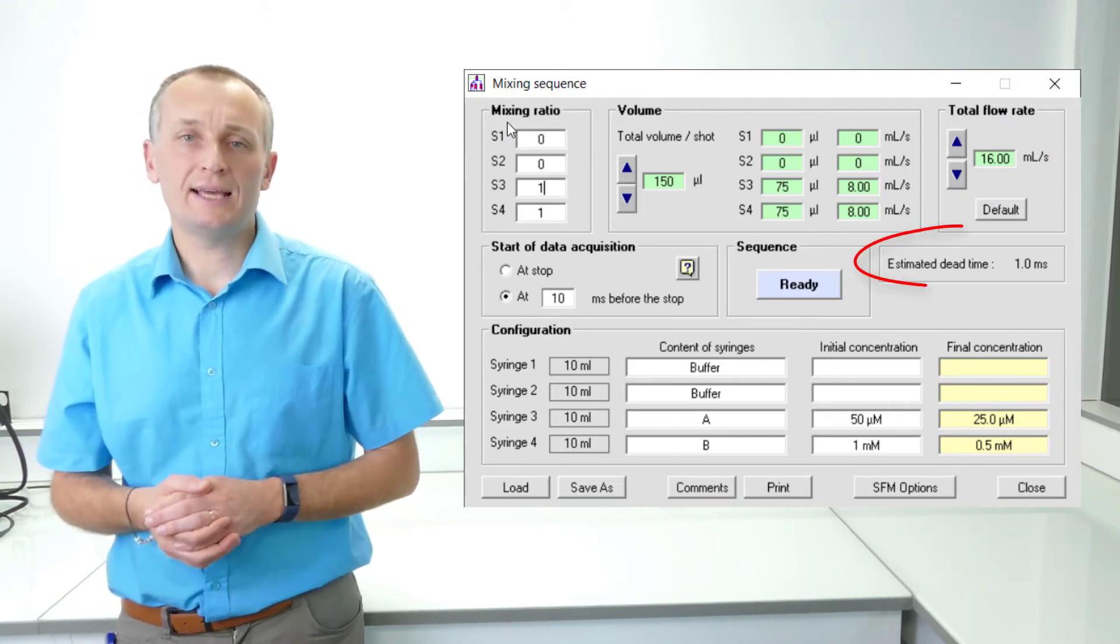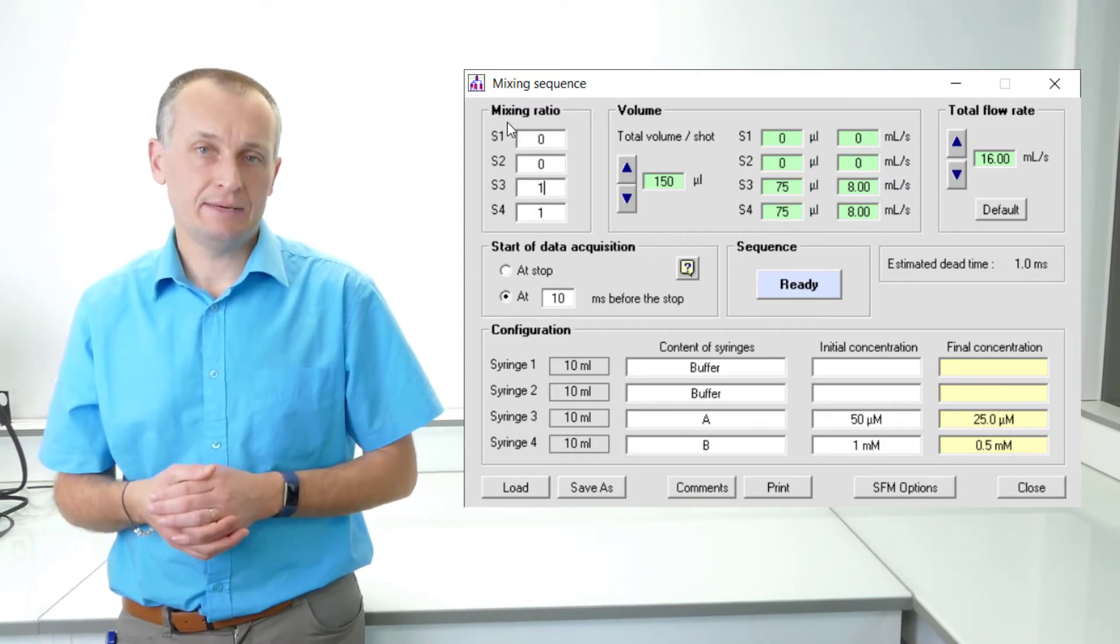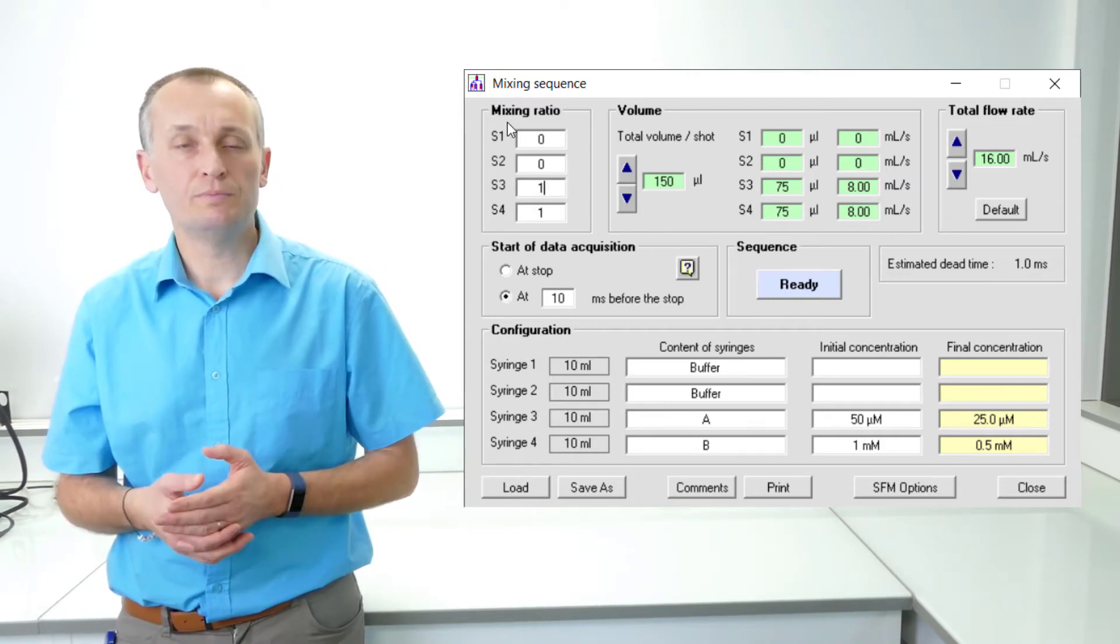The dead time can therefore be estimated by the software for each experiment. I said estimated because there could always be a small deviation on the real cell volume because of O-ring compression or because of some hydrodynamic phenomena. This deviation on dead time is in the range of 0.1 to 0.2 ms.